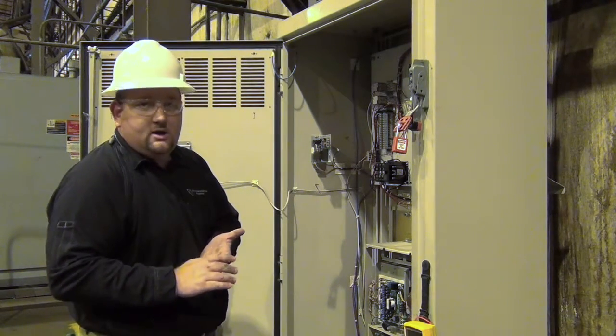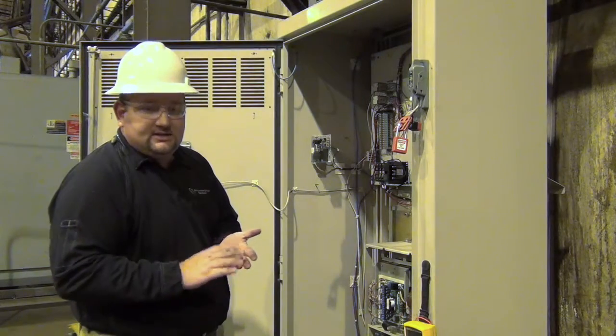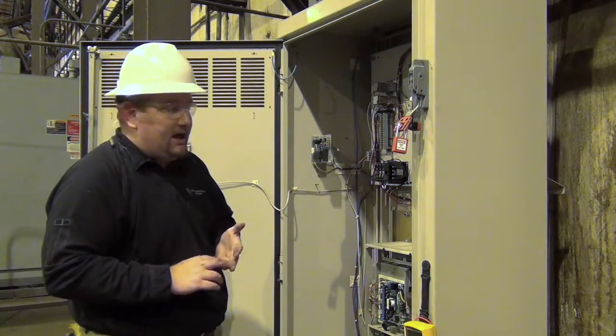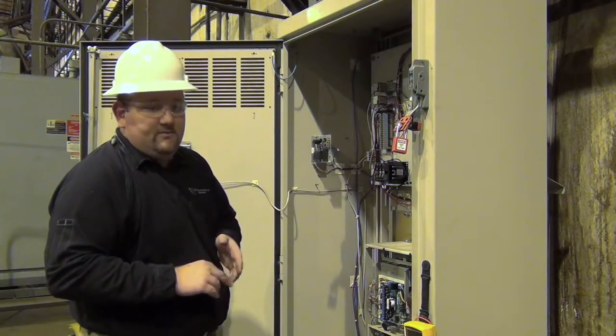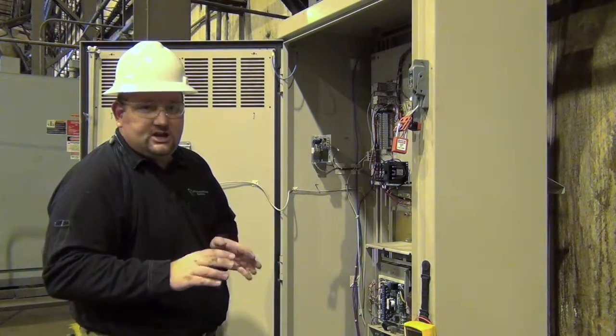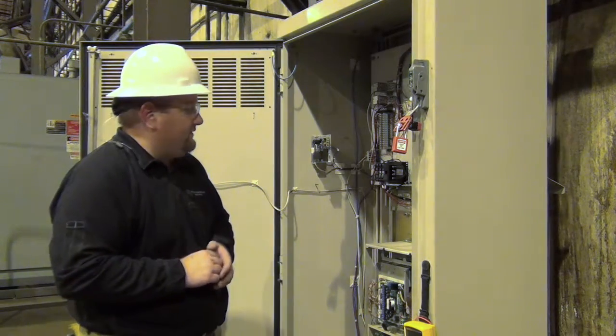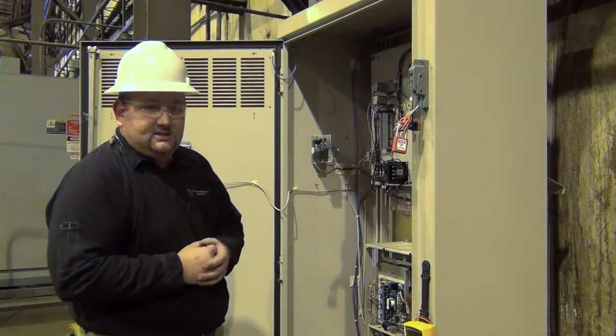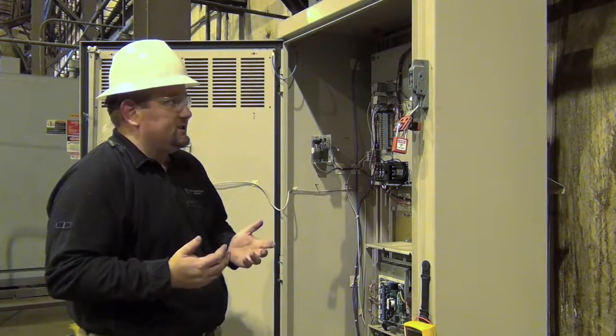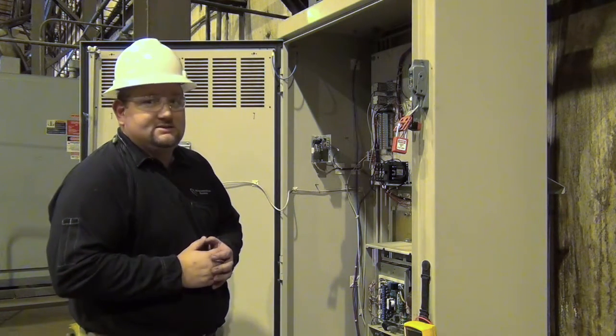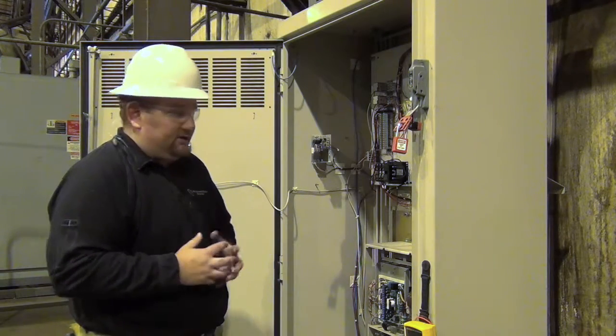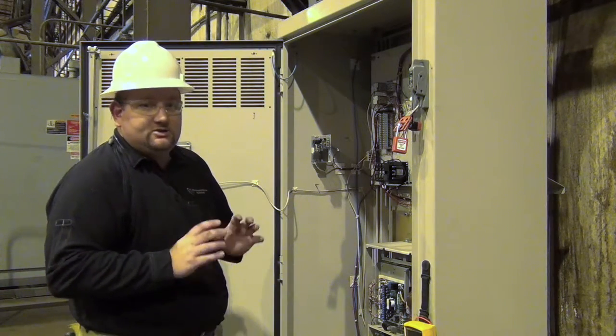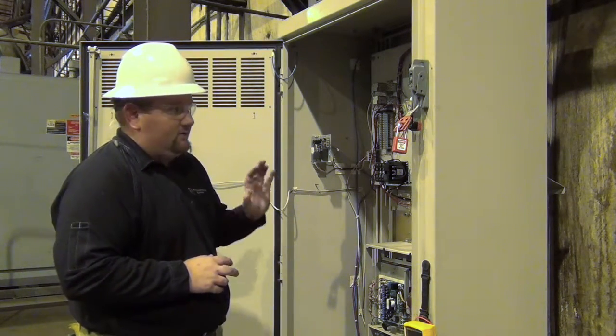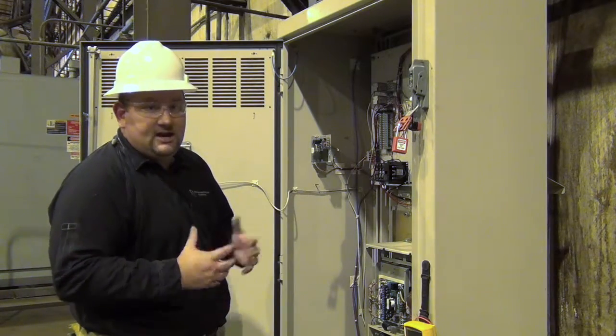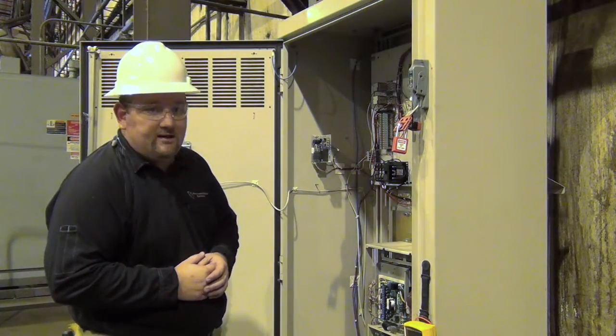Don't use water. Just use a nice terry cloth or a microfiber cloth, dry only, and then just very gently rub where you can and where it's safe to try and remove any caked debris. If it's been numerous years or decades since the equipment was maintained, you may not be able to get it fully clean, but trust me, you're still doing a great deal of good, and you're really helping the equipment out by trying to clean anything that you possibly can out of it.